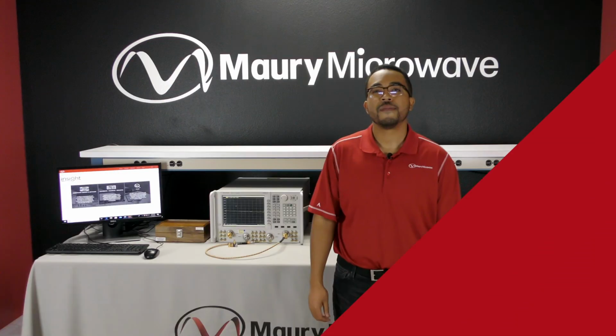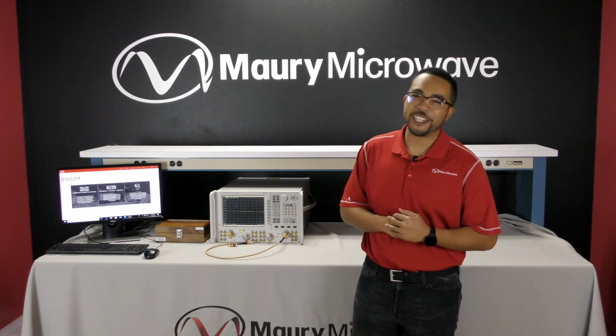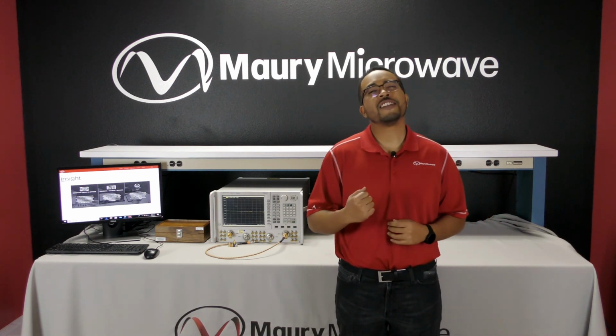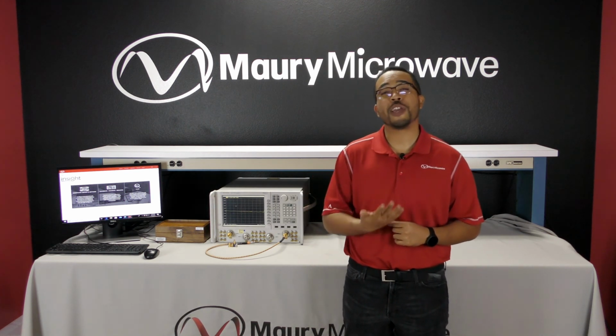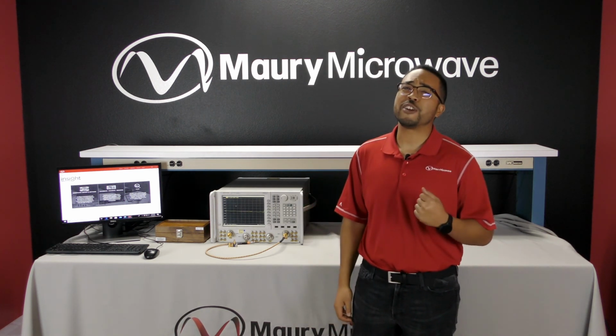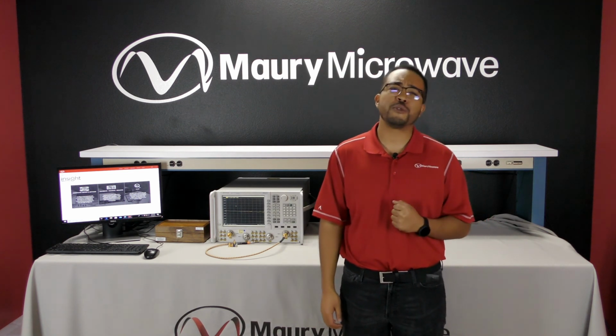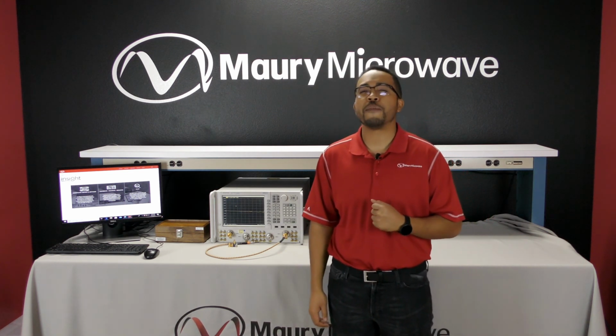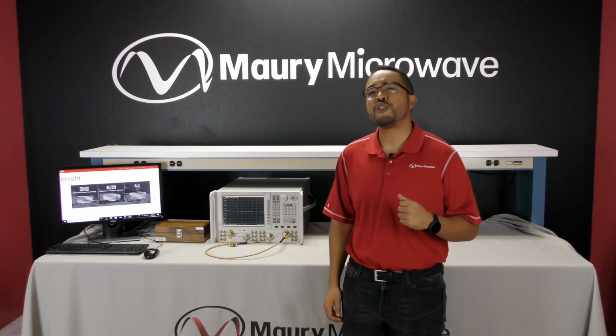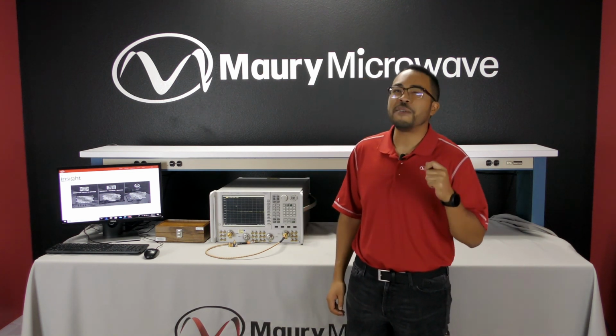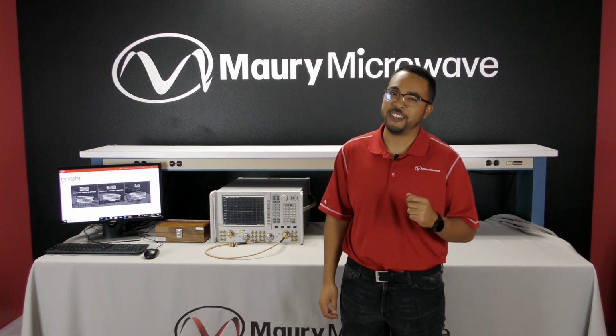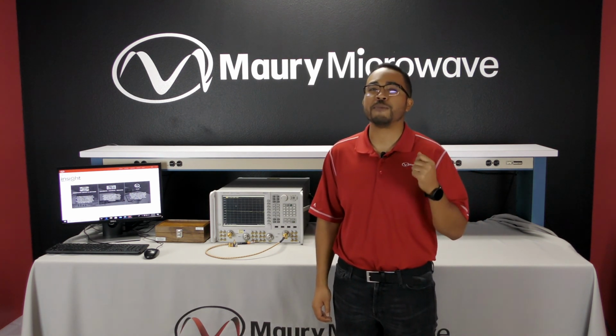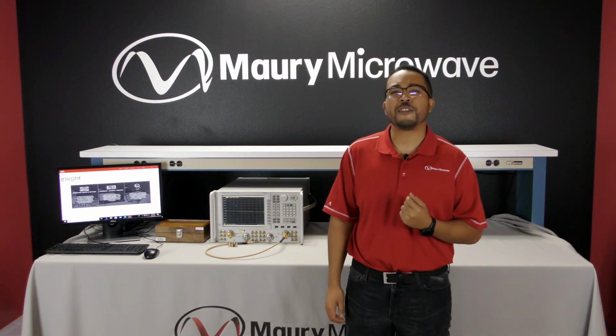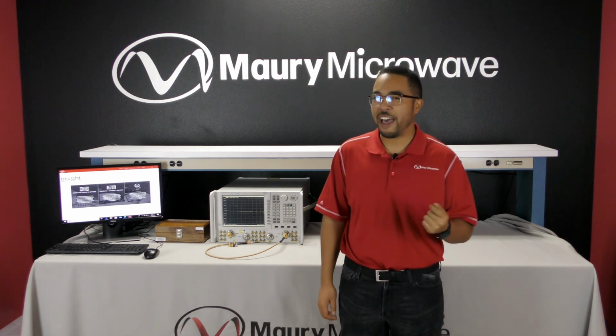This region of uncertainty can be reduced by improving the maximum contribution of each piece of equipment in the system setup. As I showed in the demonstration, your measurement isn't a line, it's a region. Measurement inconsistencies over time from system to system, from location to location, and from user to user can often be traced back to the measurement errors or uncertainties of each individual system. By characterizing each component of a measurement system, we are able to identify the contributions of uncertainty and concentrate our efforts on eliminating the primary impacts of measurement inconsistencies. We can also have faith that our measurements are substantiated, and as long as multiple sets of measurements fall within the same uncertainty boundaries, they are all accurate.